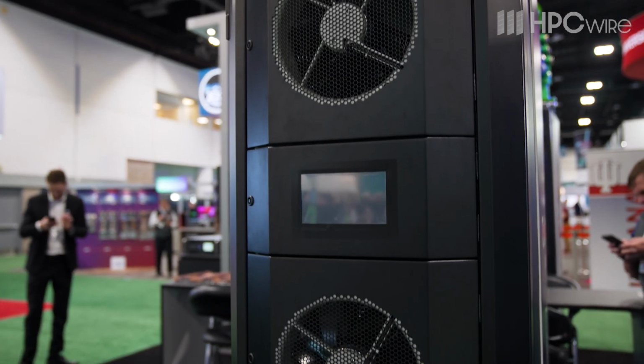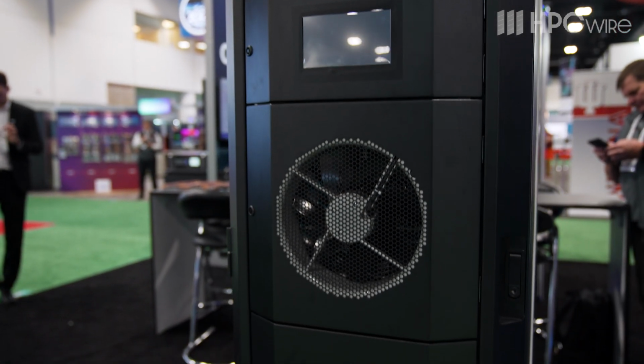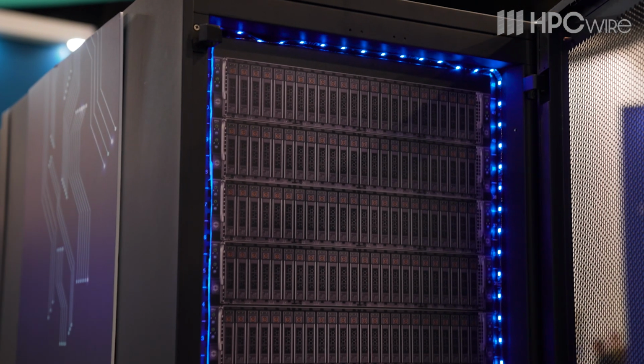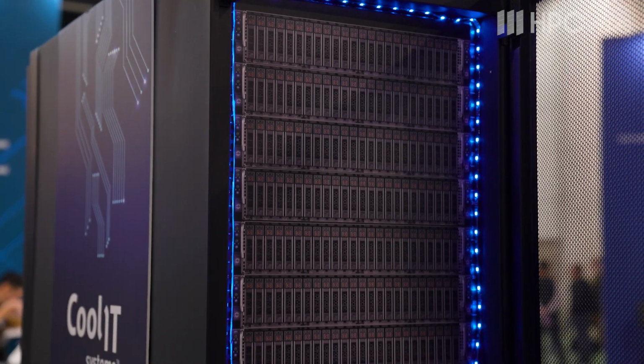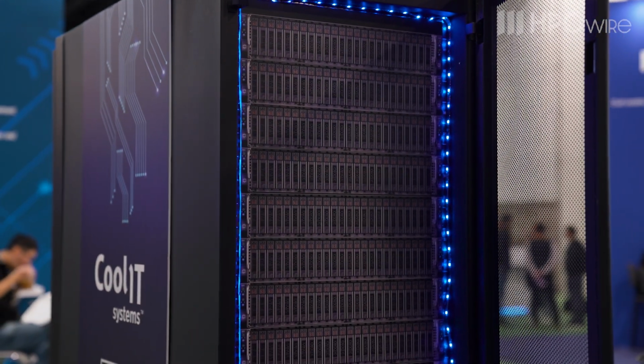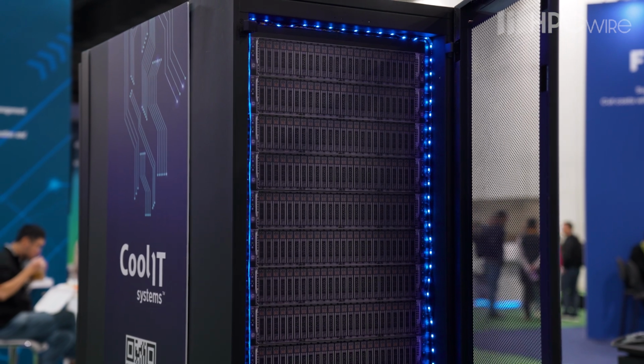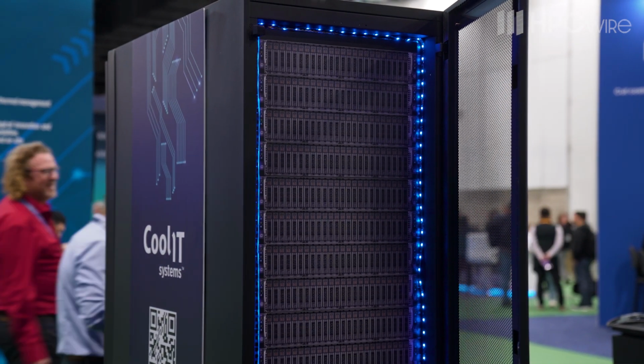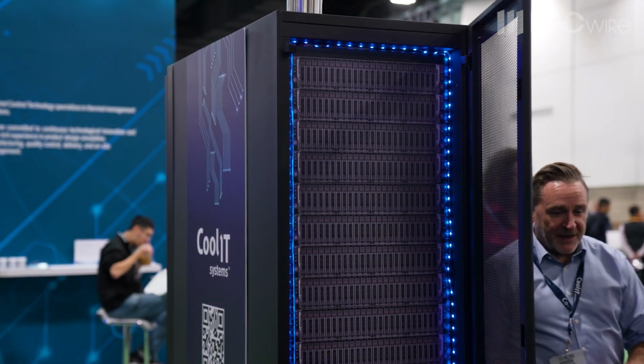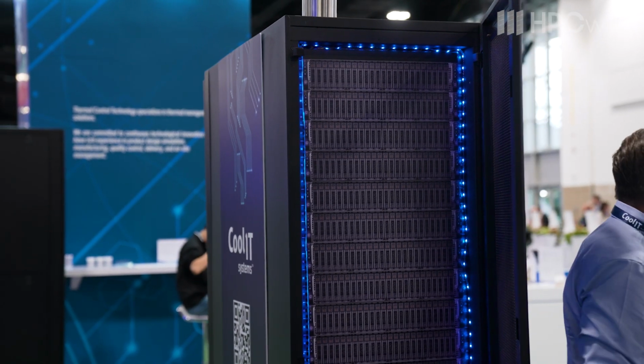We are also showing our rear door heat exchangers, designed to integrate seamlessly with direct liquid cooling systems. They're very complementary technologies — sometimes we'll deploy them on their own, since not every IT rack needs direct liquid cooling, and the rear door heat exchanger might be a great solution for some customers, data centers, or racks. But we can also integrate it with direct liquid cooling to capture remaining heat not captured by the direct liquid cooling system, or to supplement and expand the cooling range within that rack.